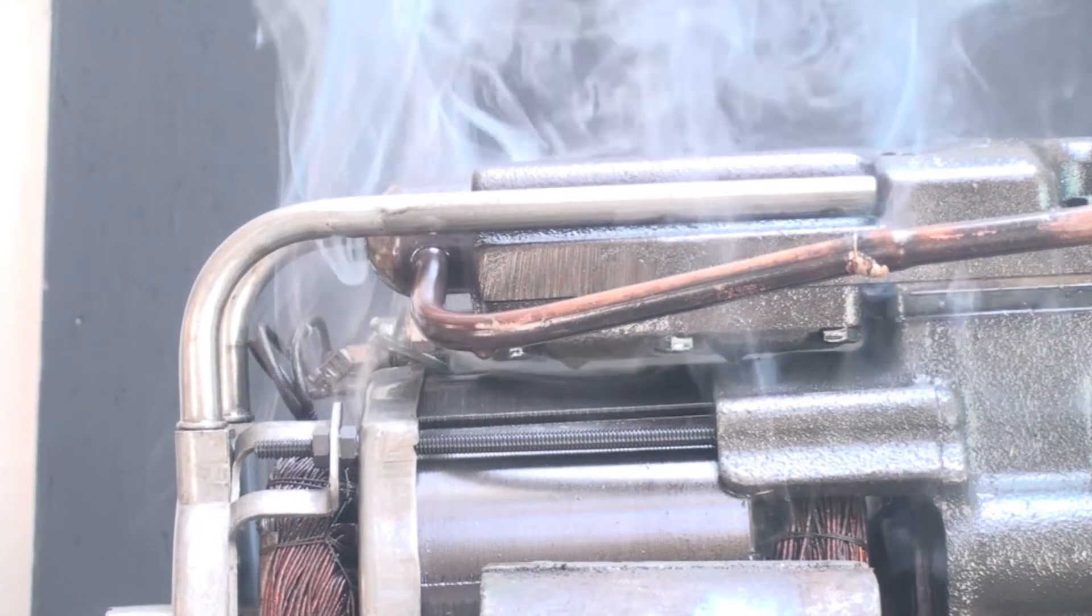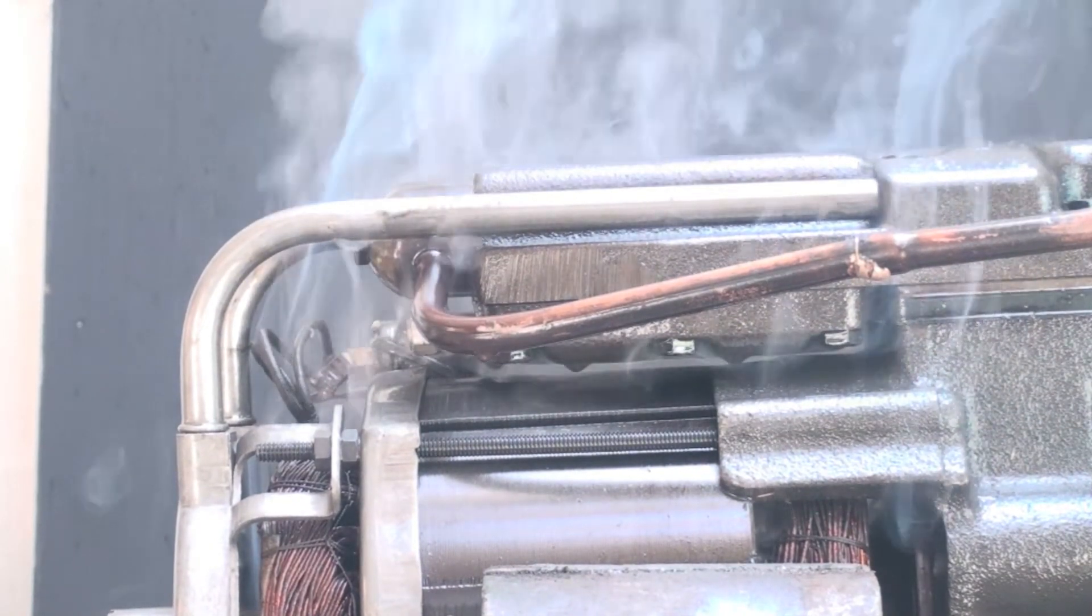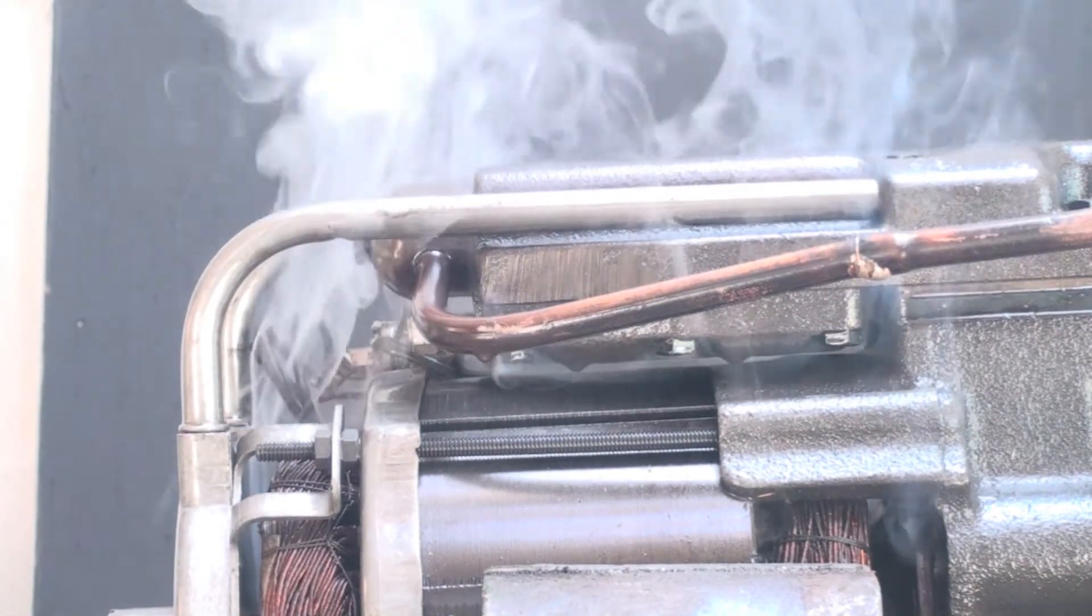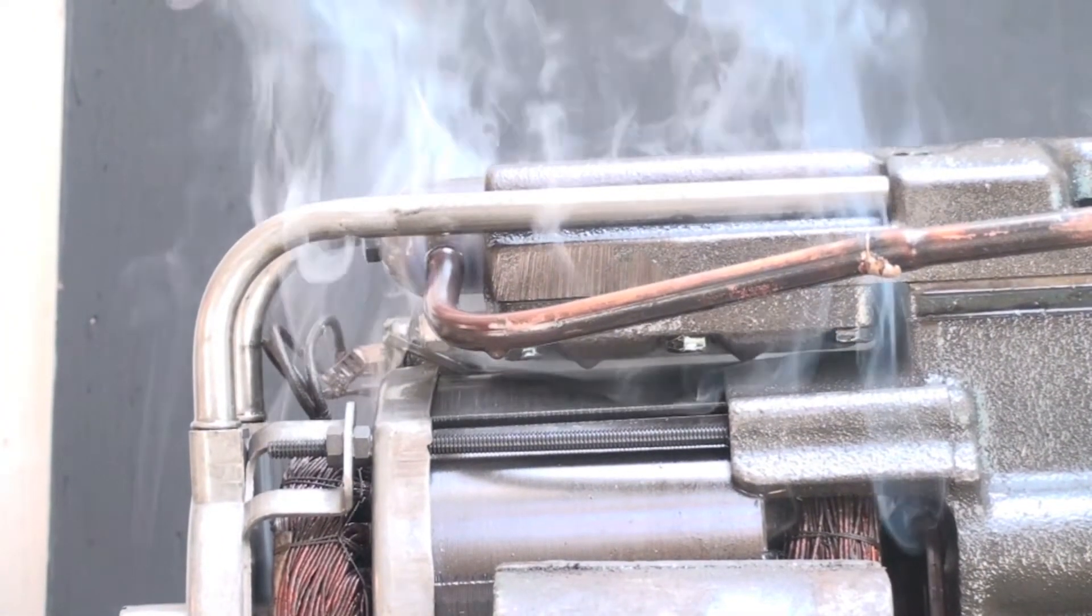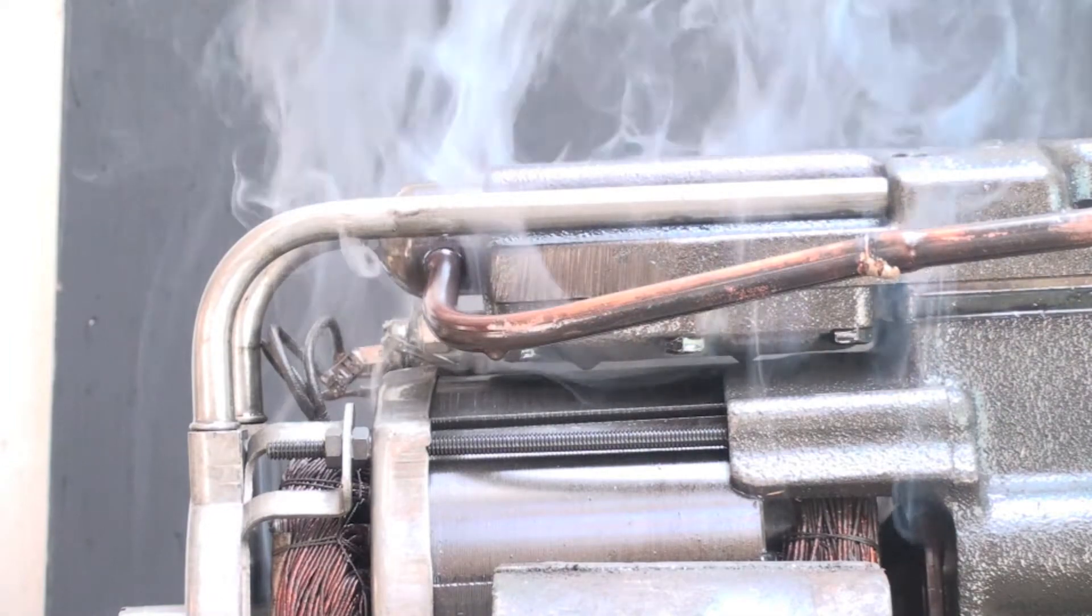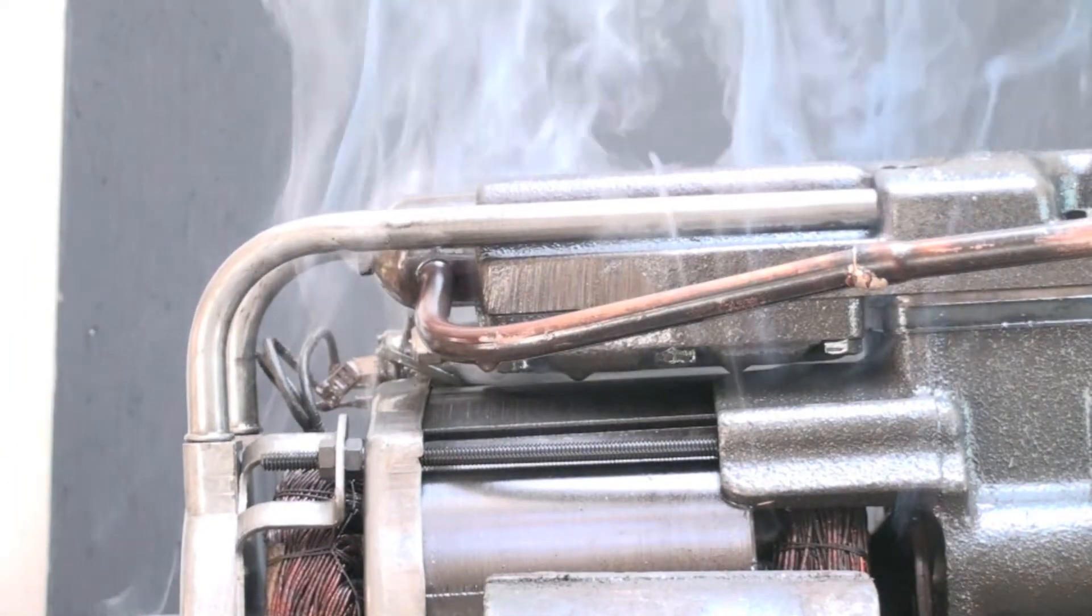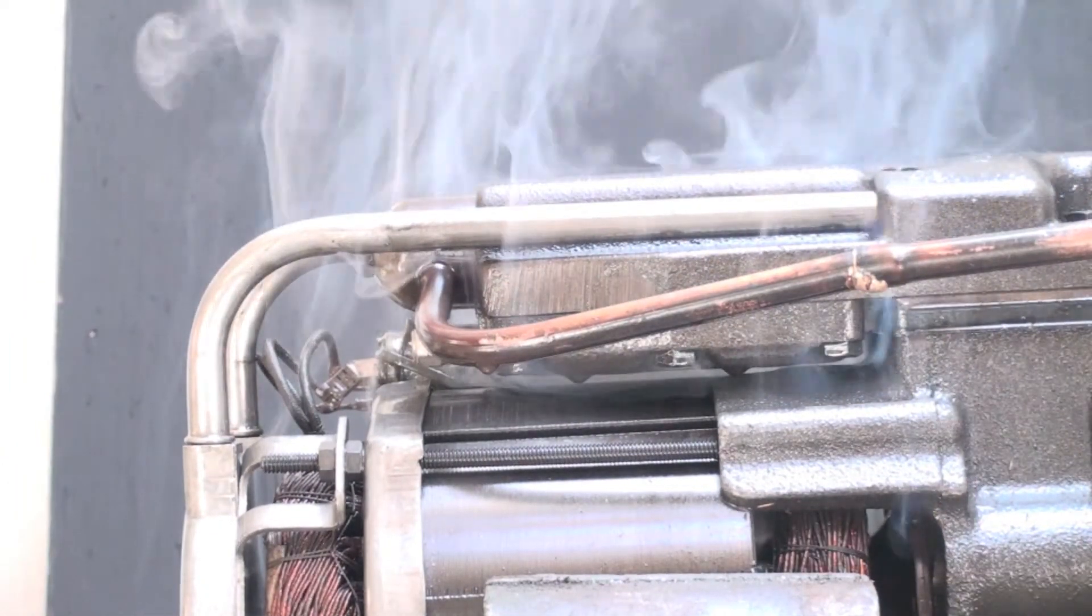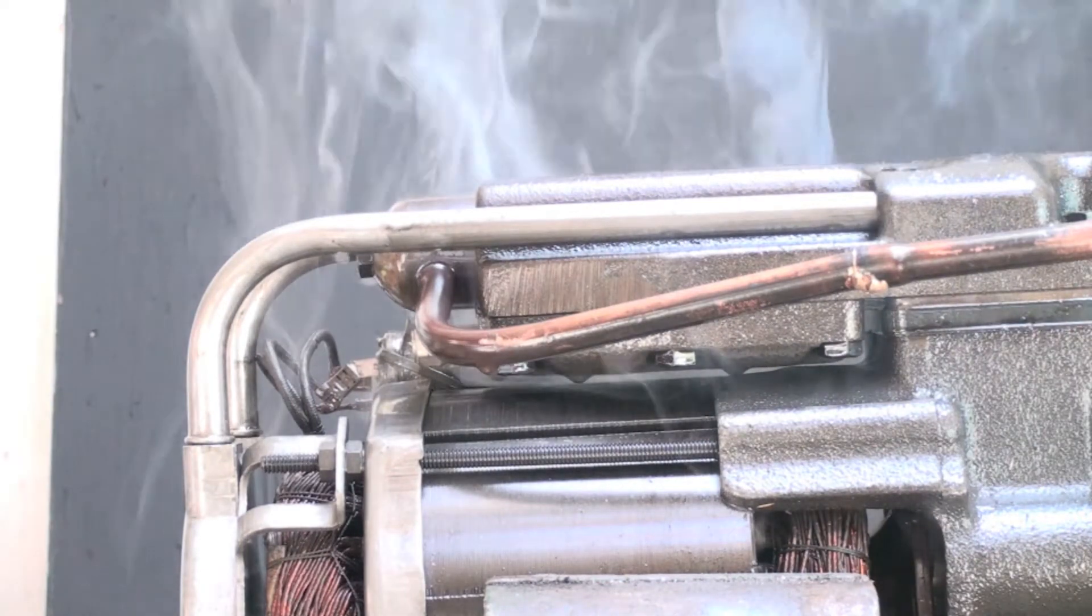Okay, I'm continuing to run this thing until the internal overload kicks off. I think at one time the breaker kicked off because it's a 50 amp breaker and we're running about 150, 120 amps. But I have been cooling down the internal overload to try it again.